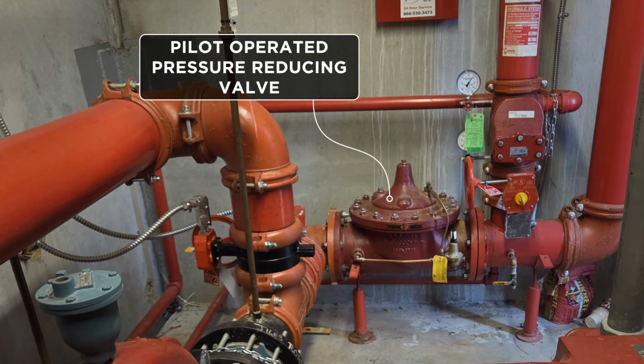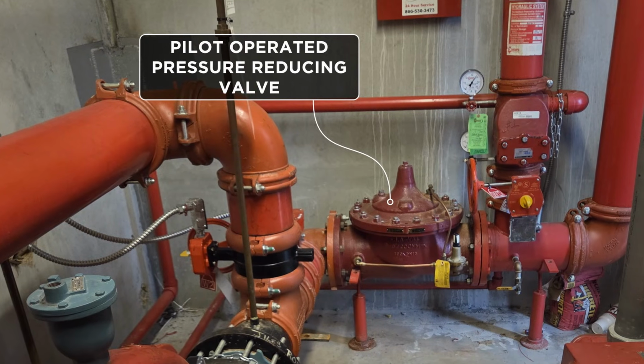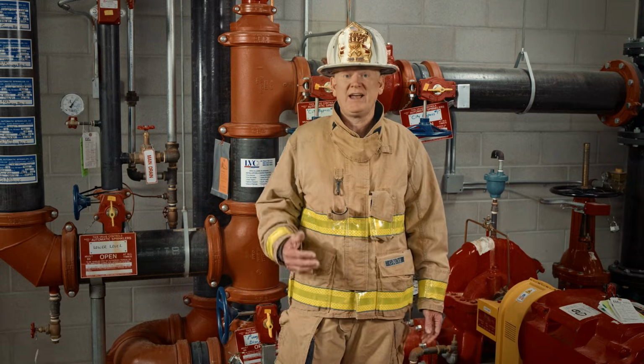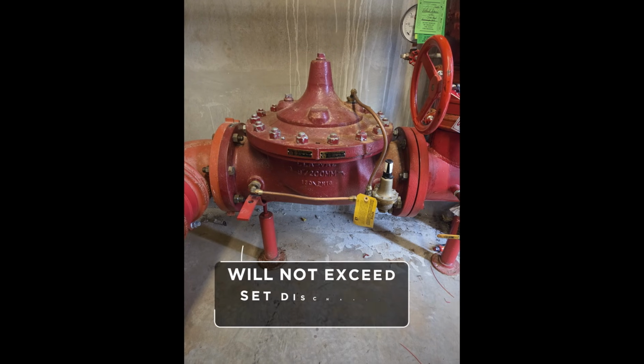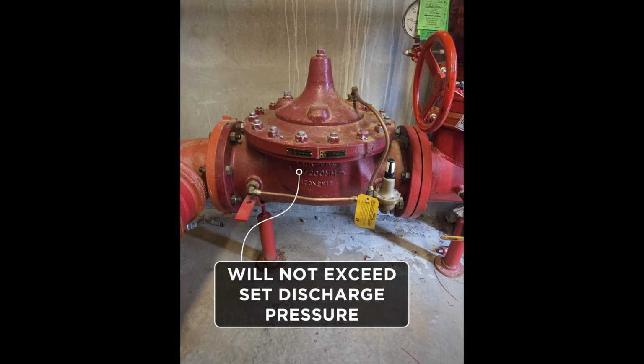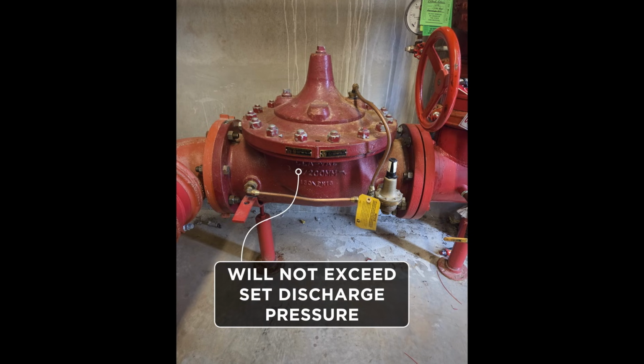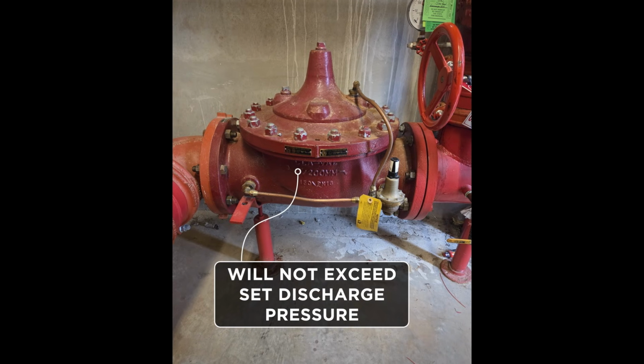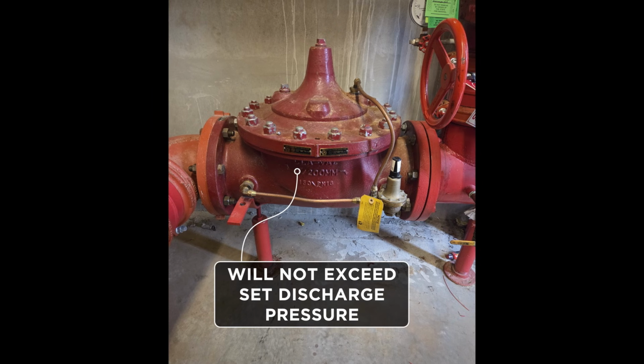Another type of valve we want to identify is a pilot-operated pressure-reducing valve. These valves will not be on every system, but if you do have them, we want to know that ahead of time. They have a maximum set discharge pressure that will not be exceeded.